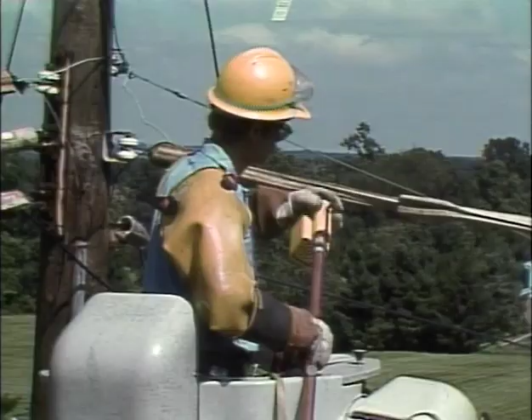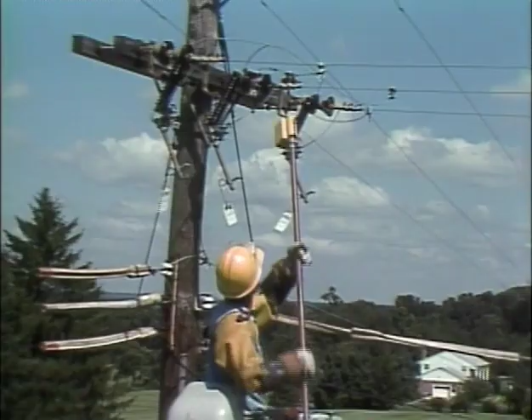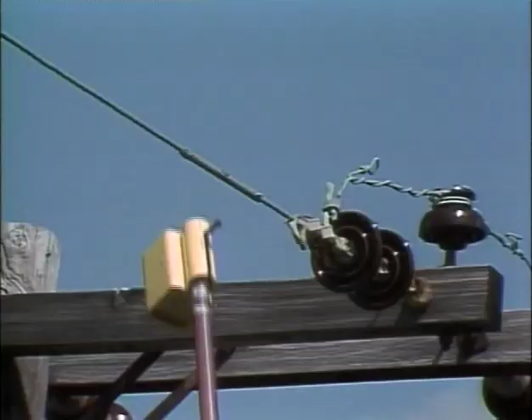To make sure the tester will detect voltage, you secure a hot stick in the slotted tube and extend the tester to an energized source. The hot stick keeps you a safe distance from the energized lines. Again, the sound indicates the tester works on a live source. Now you can test the lines at your job site. This 13 kV circuit is within the operating range of the tester. The tester is extended up to each line until it touches. If there is no sound, the results indicate that the lines are dead. After testing for dead, check the tester a second time to confirm the results of your circuit test.